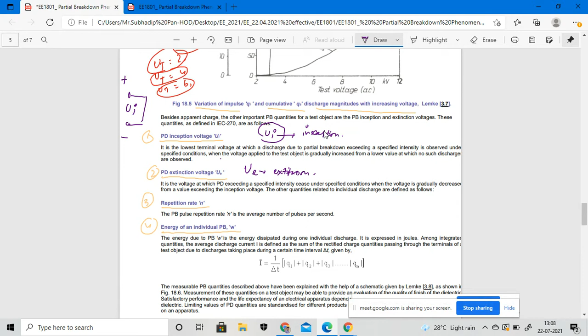What is this? It is the voltage at which the partial discharge falls below a specific intensity under the specific condition when the voltage is gradually decreased. The inception voltage is when the voltage is gradually increasing, but in the case of the extinction voltage, the voltage is gradually decreasing from a value exceeding the inception voltage. The other quantities related to the individual discharge are the repetition rate, and the fourth one, the energy of the individual partial breakdown.